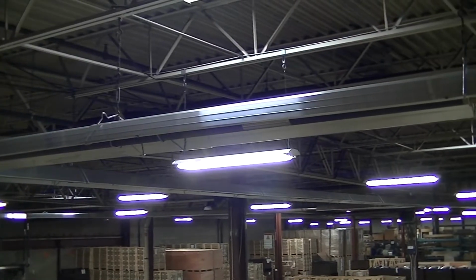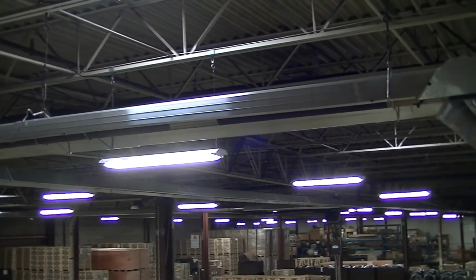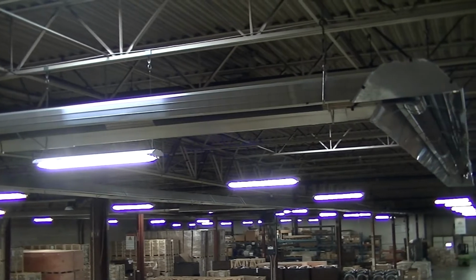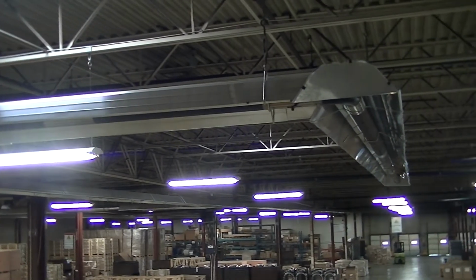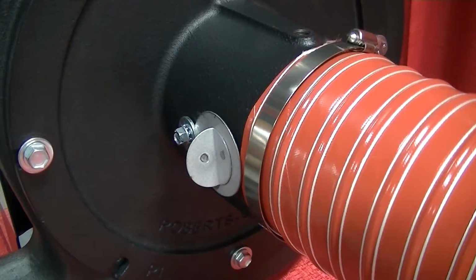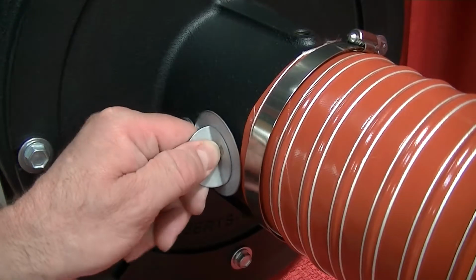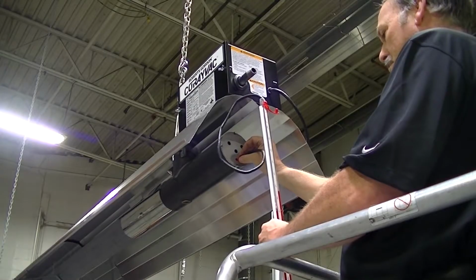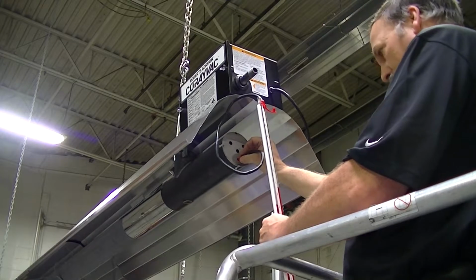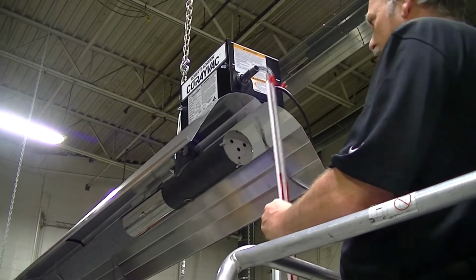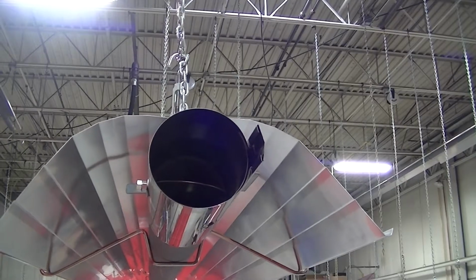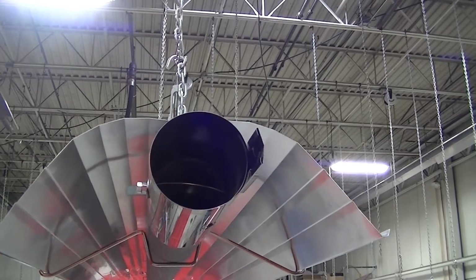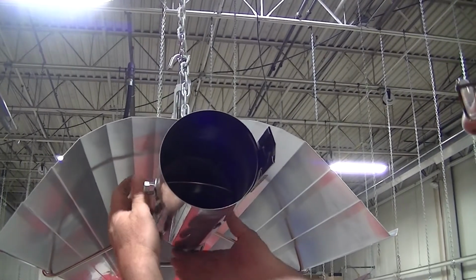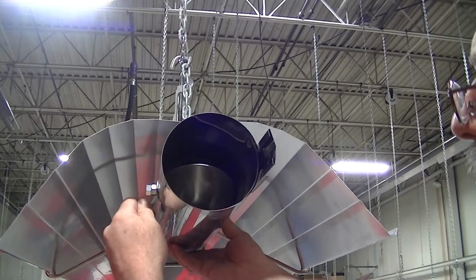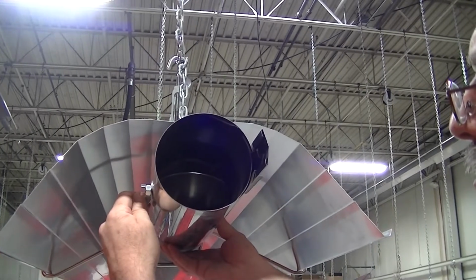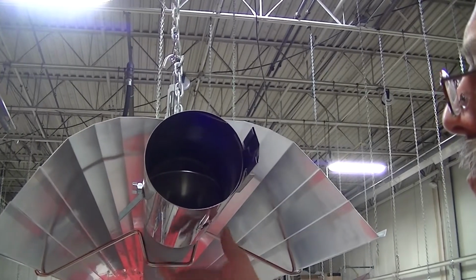When the system is symmetrical, all branches are the same length. When you have a system that has different length branches, first adjust vacuum using the damper on the inlet of the vacuum pump, as in the previous step. After the longer branch is adjusted to 2.5-inch to 3-inch water column, locate the damper coupling at the T leading from the shorter branch. Now, adjust the vacuum on the shorter branch by opening or closing this damper to achieve the negative 2.5-inch to 3-inch water column.